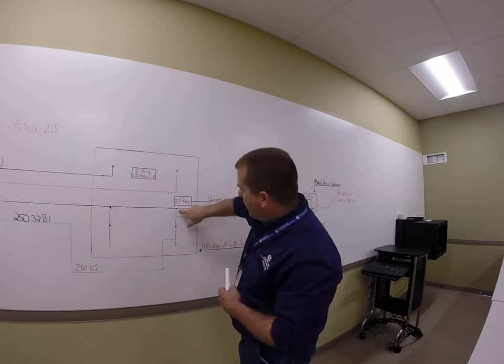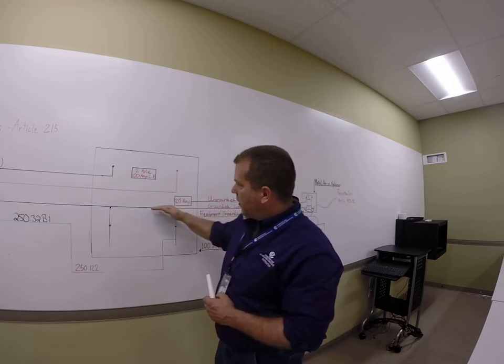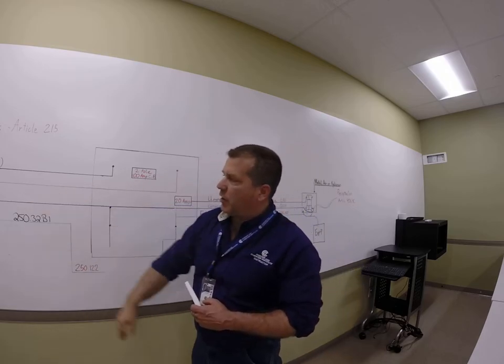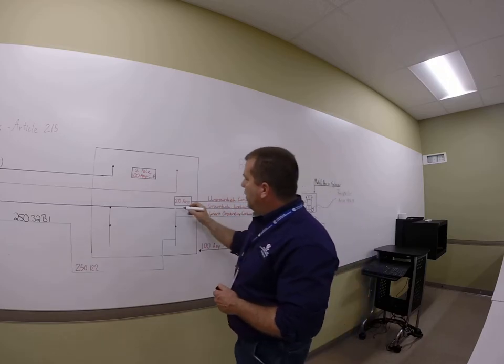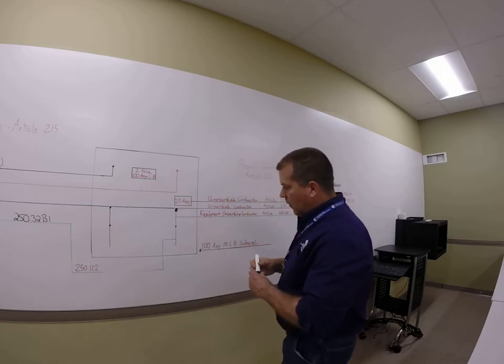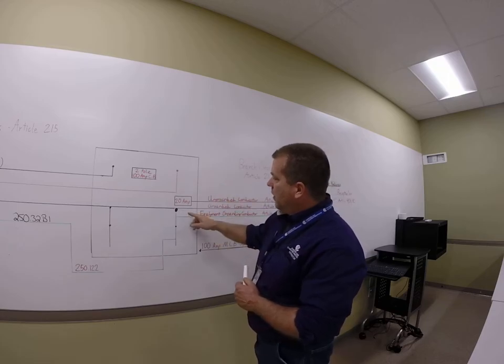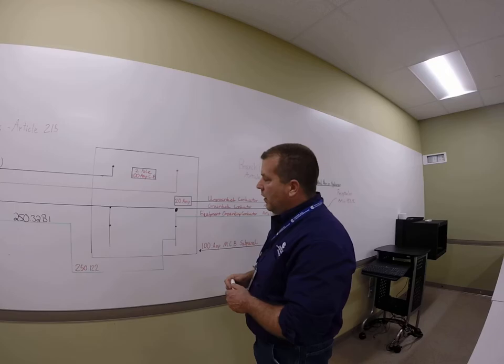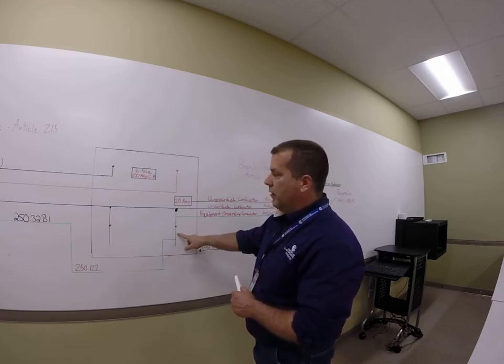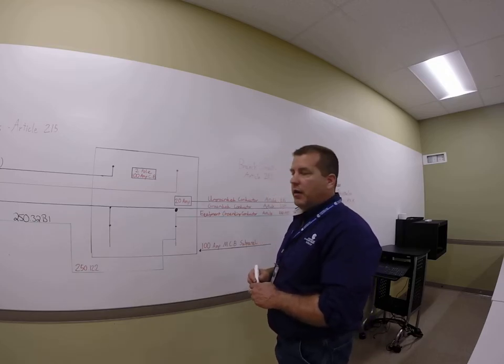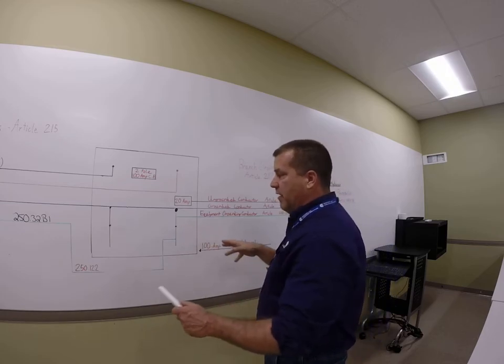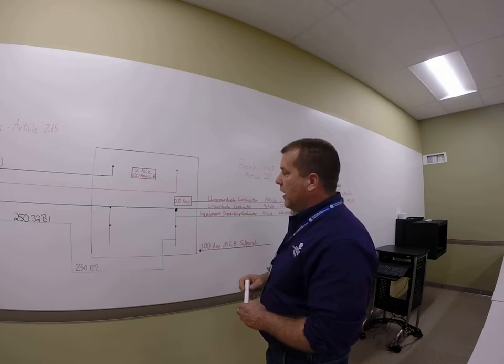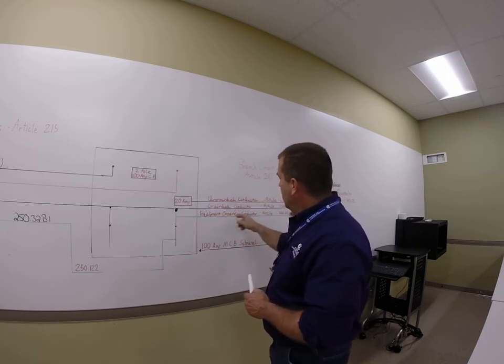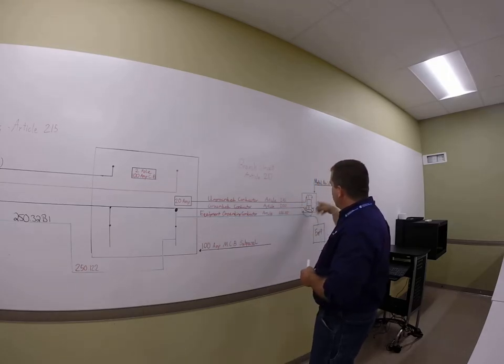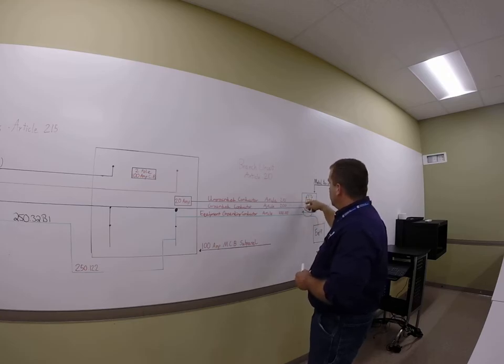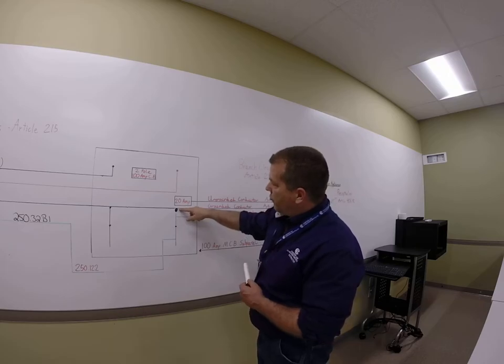In the real world, this is isolated in the subpanel. So that neutral current has a nice clean path to pick up the neutral wire back to the service and have no issues. But if I go putting the main bonding jumper in here by accident, all of the branch circuit neutral conductors can incidentally also take this parallel path to ground. And what that does is it could accidentally put ground current on your normally not current carrying metal parts. If that happens, anything that you touch that might be metal, and if you touch a different potential, you pose a shock hazard on that surface because that ground current now exists. So if you imagine you've got a 10 amp load plugged into this receptacle, well, we got 10 amps coming back on that neutral, and now all of a sudden these electrons see this path they can take.